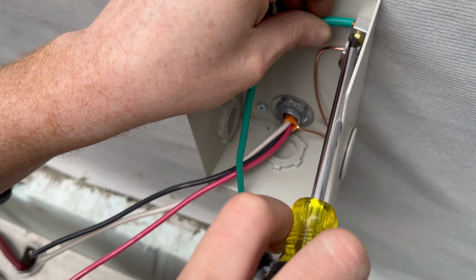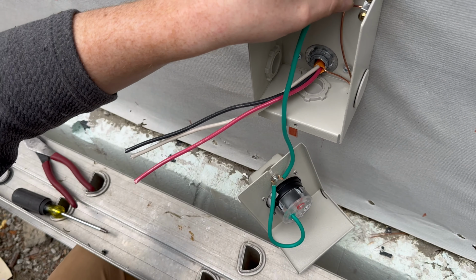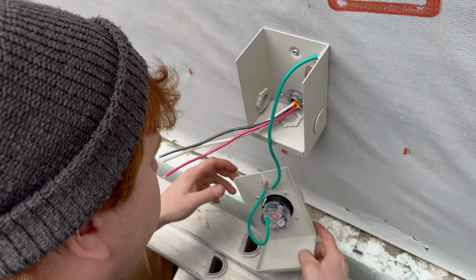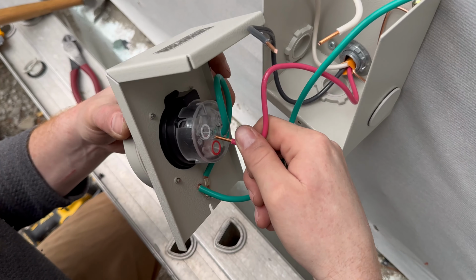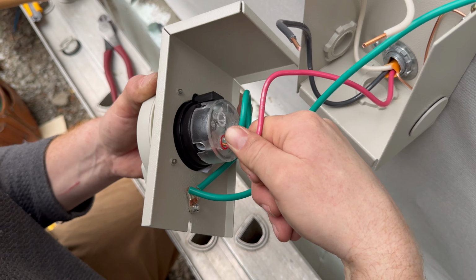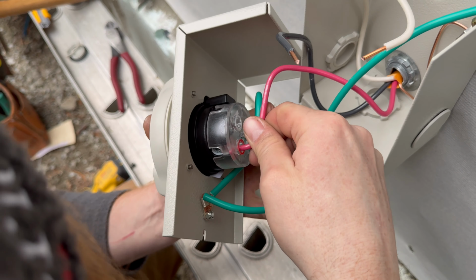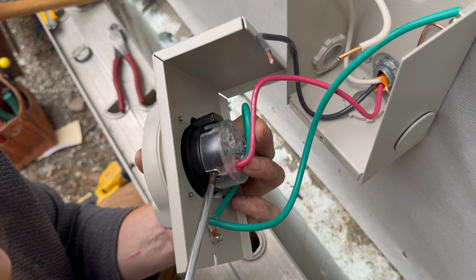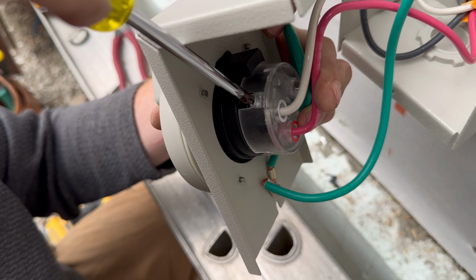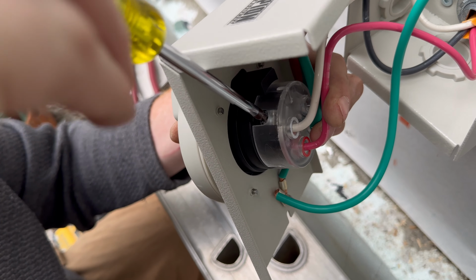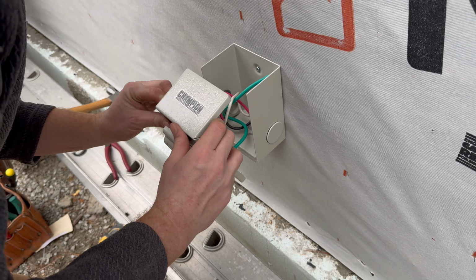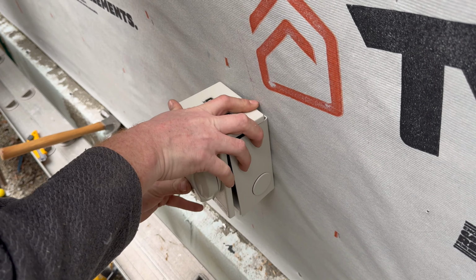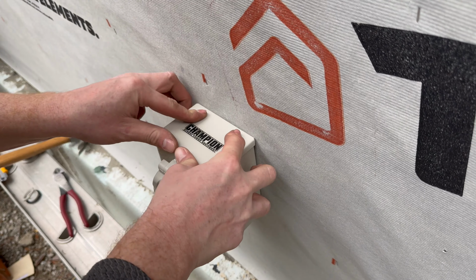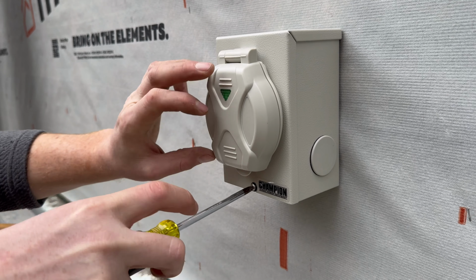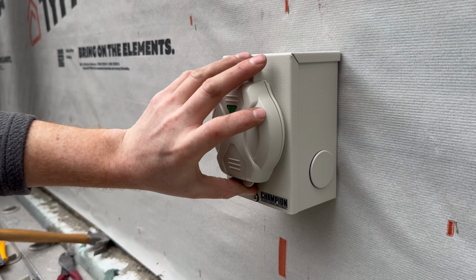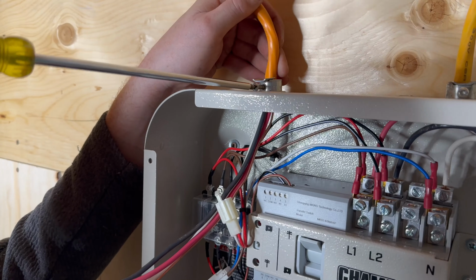Make the appropriate connections within the inlet box. So that would be the green ground wire that grounds the whole box. That goes to the ground lug. And then the black, red, and white wires go to the appropriate connections on the actual inlet connector itself. Finish up with this part of the installation by securing the cover of the inlet box, and then you can move on inside to complete the connections at the transfer switch panel.